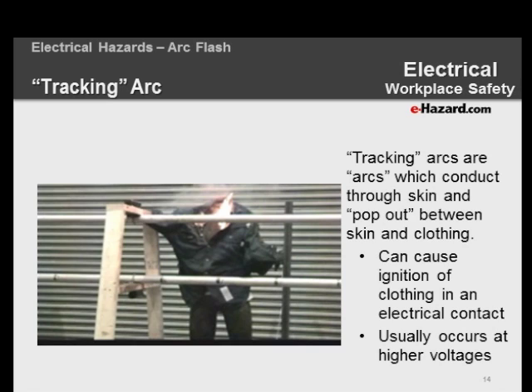So if you're at higher voltages, electrical contact can actually ignite clothing underneath. That arc was underneath the clothing for just 2 cycles, a 30th of a second. The Arc Flash calculation here was only 1 calorie, which you'd never think would be enough to ignite the garment, but it was. The key is training on full-blown electrical safety, not just throwing Arc Flash PPE at workers.